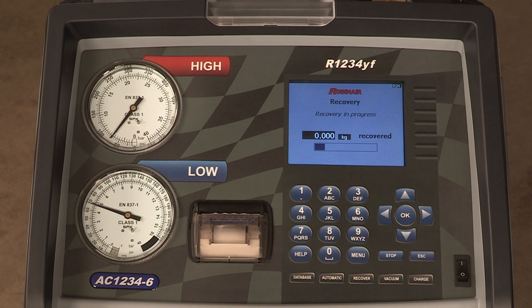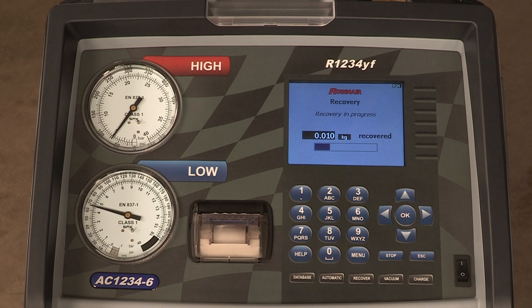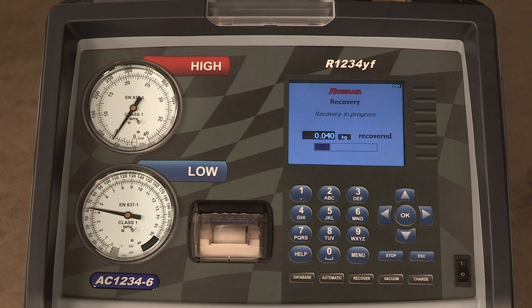After the oil drain is complete, the machine displays a summary of gas recovered. The amount of oil that was recovered from the system is the amount of new oil that should be charged into the AC system after the evacuation is complete. Dispose of used oil according to government regulation.